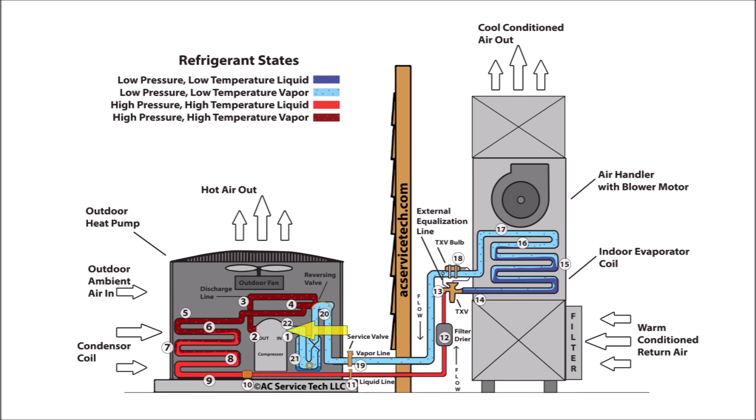At step one, you have the low pressure, low temperature, superheated vapor entering the vapor compressor. Then at step two, the high pressure, high temperature, superheated vapor exits the compressor. For the refrigerant, anytime the pressure increases, temperature increases — likewise, anytime temperature increases, pressure increases. So what's happening is the compressor is increasing the vapor pressure in order to increase its temperature.